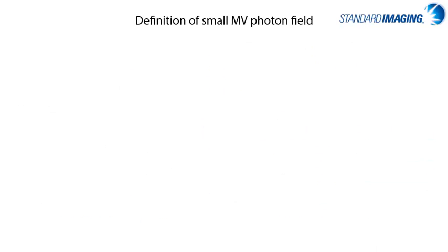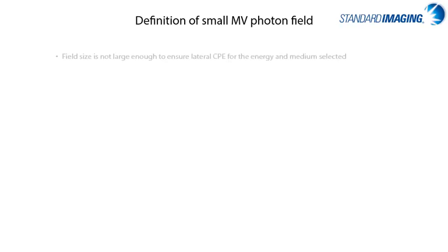So it should be clear now that the term small field is a bit of a loaded question if you ask someone to define it as there really is no simple definition. However, for the purposes of this talk and in agreement with the forthcoming AAPM TG-155 report, the main characteristics are as follows in that the field size is not large enough to ensure lateral CPE in the medium of interest for the energy selected.